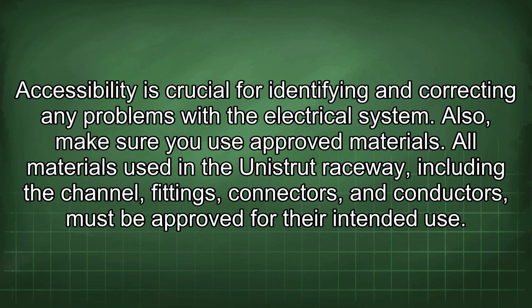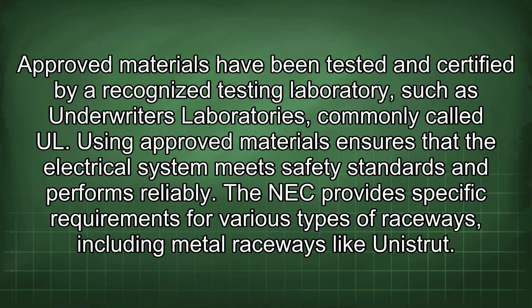Also, make sure you use approved materials. All materials used in the Unistrut Raceway, including the channel, fittings, connectors, and conductors, must be approved for their intended use. Approved materials have been tested and certified by a recognized testing laboratory such as Underwriters Laboratories, commonly called UL. Using approved materials ensures that the electrical system meets safety standards and performs reliably.